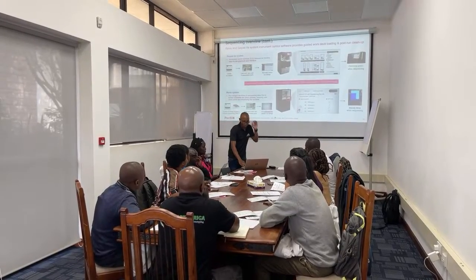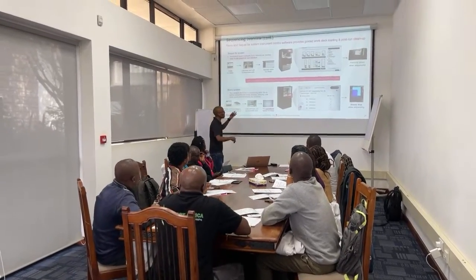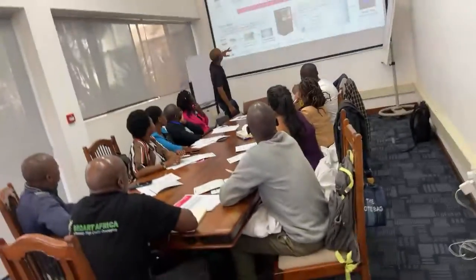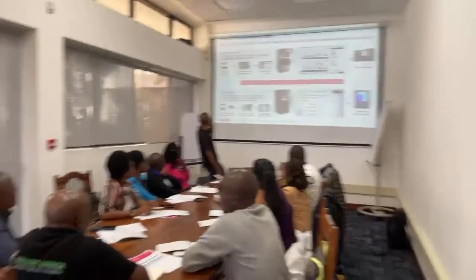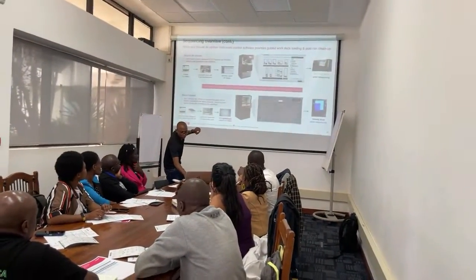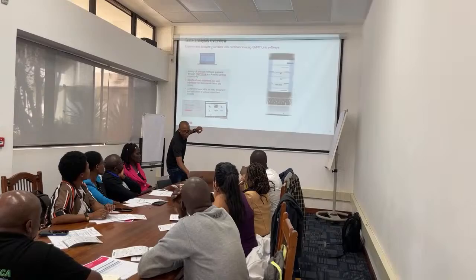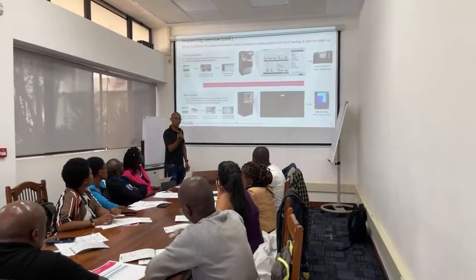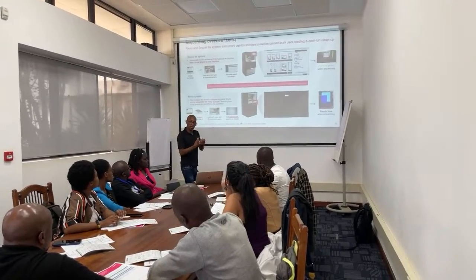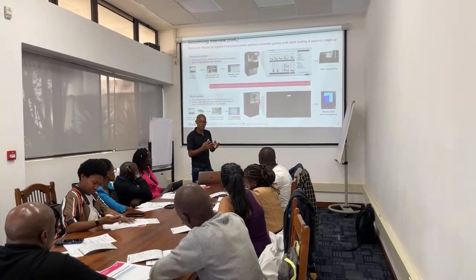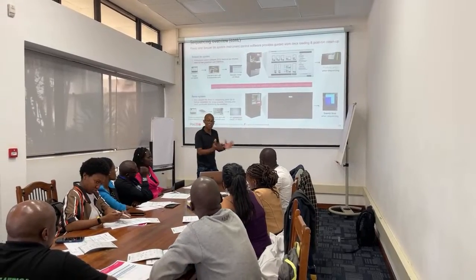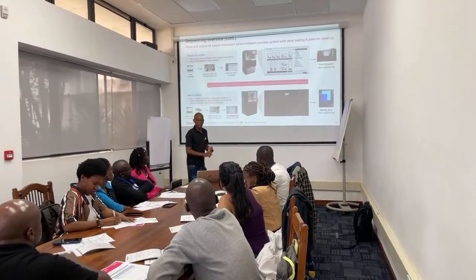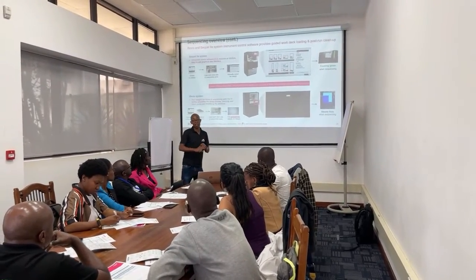And then, yeah, so this is the software that we used. Once you've generated the library, we go to what we call, so the software is called SMRT Link. We do 2 things with the library once we have it. Sample setup is where it tells us how much of the annealing primer you use and how much of the polymerase you use, based on that library.